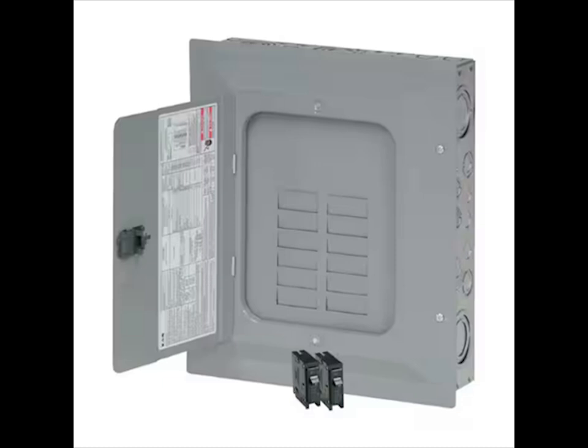To connect this subpanel to the main, I used 2-gauge aluminum wire for the two power feeds and the neutral, 4-gauge aluminum wire for the ground. Per code, the neutral and ground bars are separated in the subpanel. The subpanel neutral is only tied to the main panel neutral.